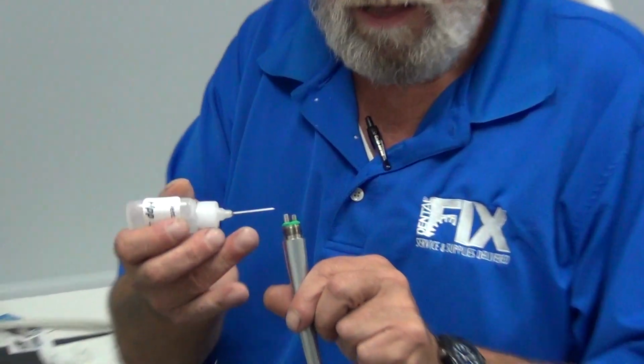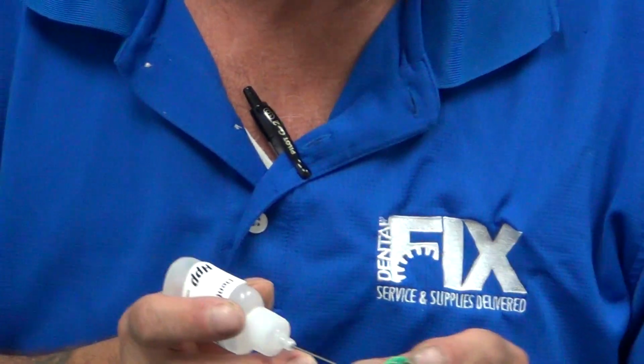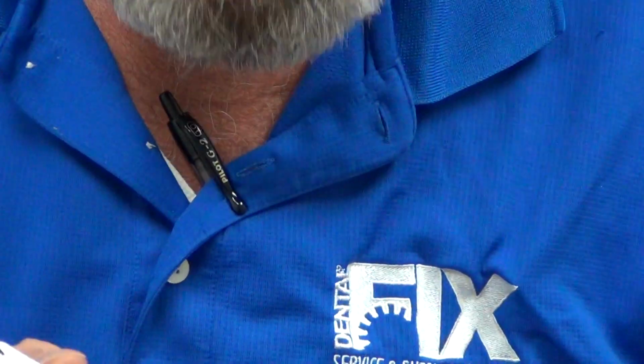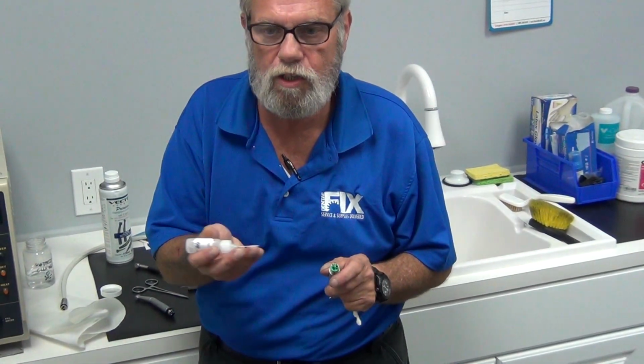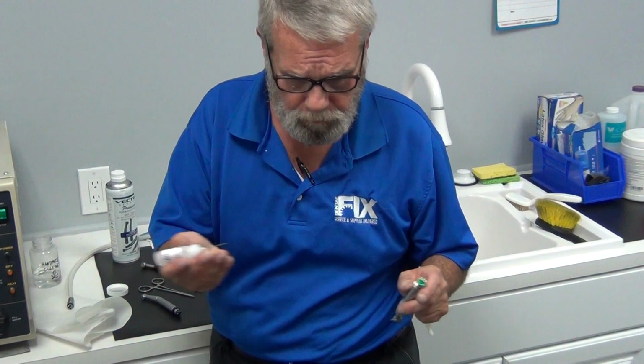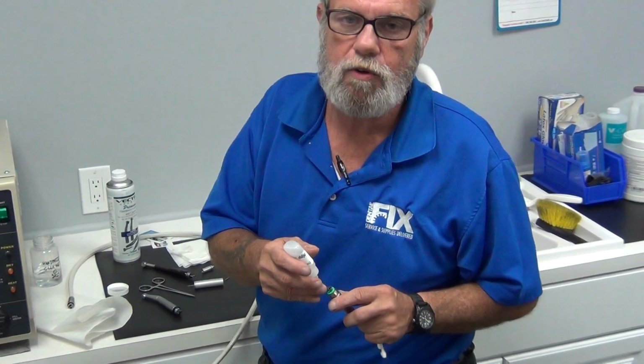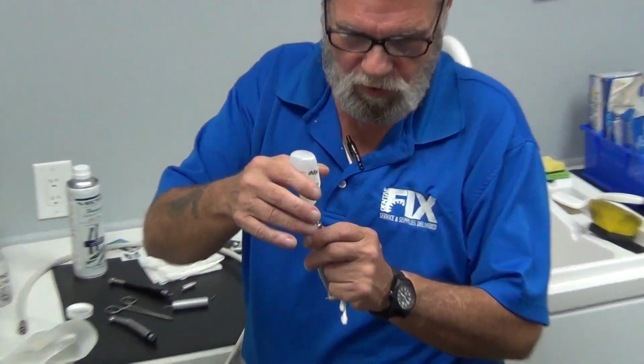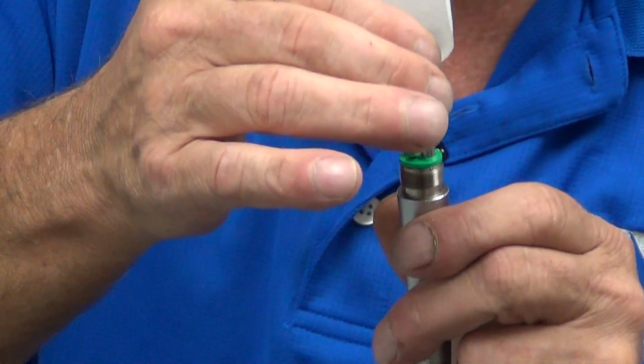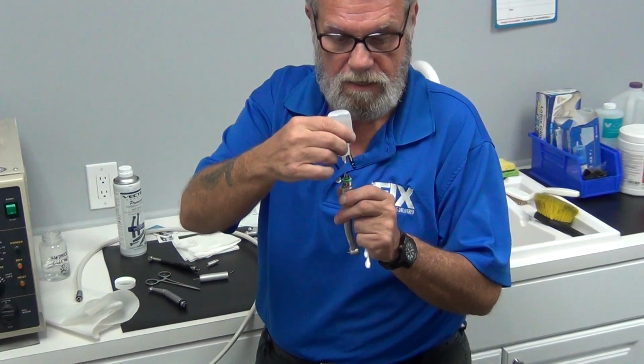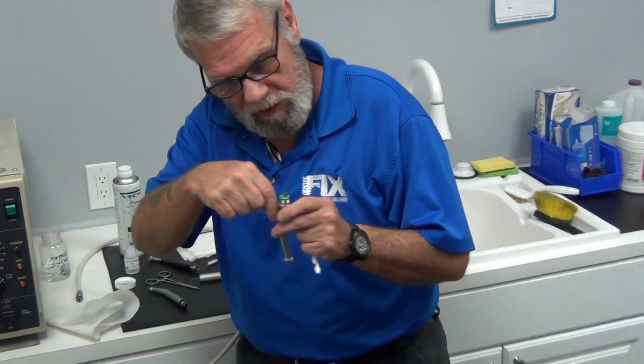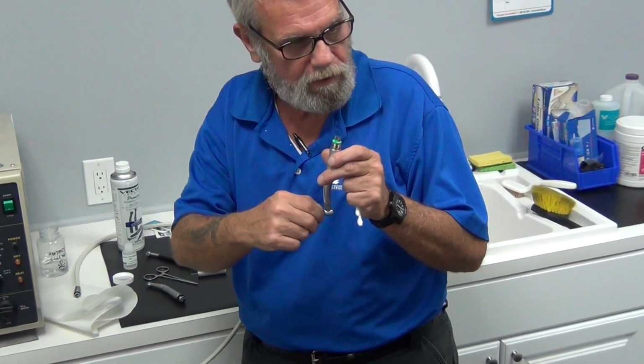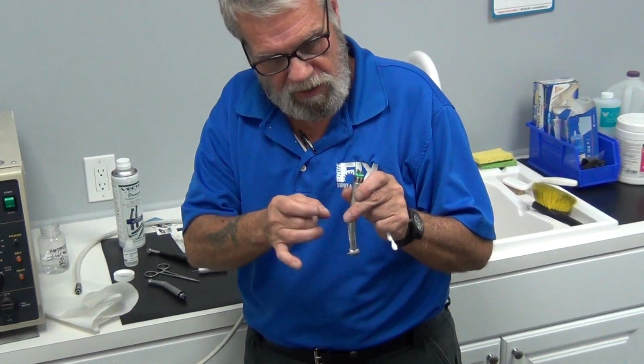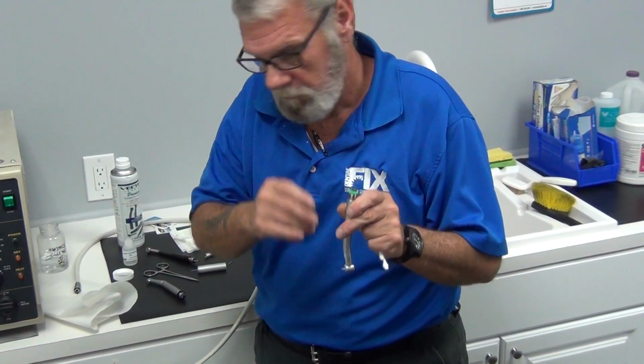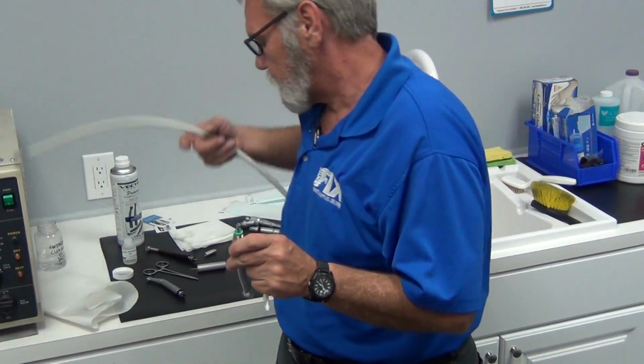This is a standard 5-hole connector, 4-hole connector that you just screw on. Down the drive air line. Now which one is the drive air again? The small of the big one. Smallest of the big. Very good. Always remember the smallest of the big. You guys all learned that in school anyway. Smallest of the big. And don't go crazy with the lube. You want to get your needle down in as far as possible. 1, 2 drops with the handpiece down. Because why? The gravity with the handpiece down actually helps pull the oil down into the turbine. And the turbine's where we want the lubricant. Give it a nice little thump to get the air bubbles out of it. Get the oil distributed.